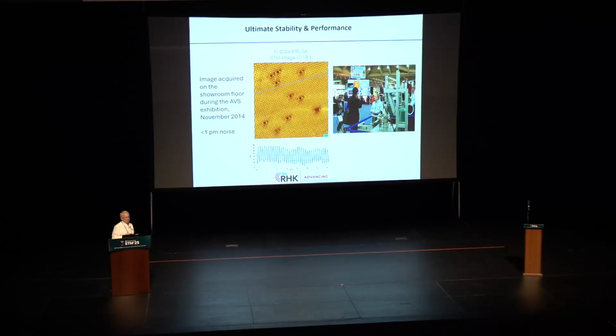In the very beginning, everybody thought closed cycle would be a pretty good idea, except nobody thought it would work due to the high levels of vibration. So seeing is believing. We took a complete system to many international conferences around the world, including one here in Korea. The microscope is running in UHV at low temperature. Normally you'd move the noisy components, the chiller and the compressor, away, but there's no room inside of a booth. So literally the compressor and the chiller were almost touching the microscope and still getting beautiful atomic resolution.